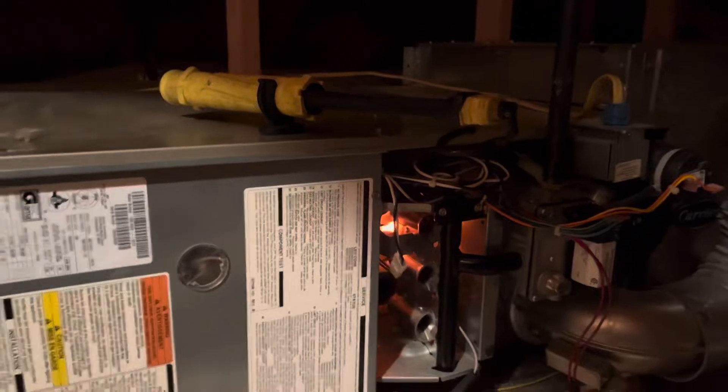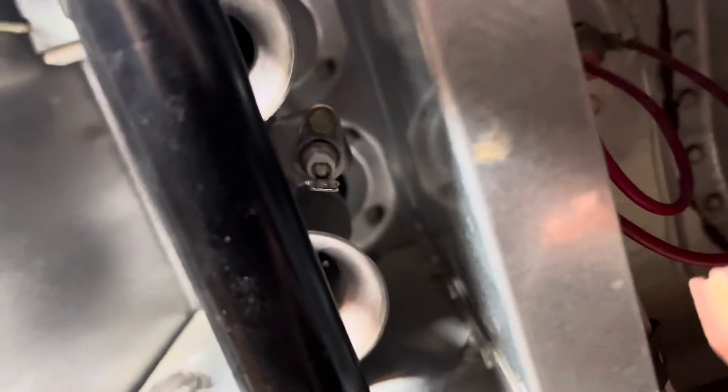All right, that's probably going to be a dirty flame sensor. Let me turn off the power and pull the flame sensor. The flame sensor is right here. There's the wire that goes to it, in case anybody's not an HVAC guy.